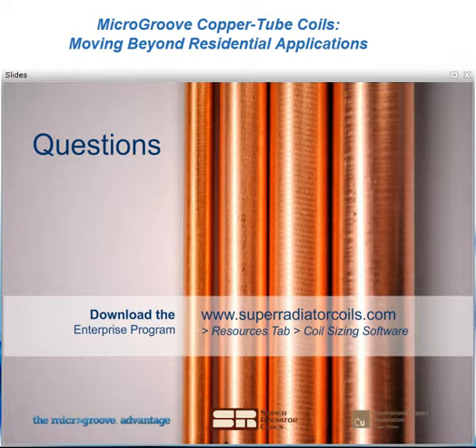The first one is, you have talked about less metal, but do the coils themselves actually cost less? That's a great one, Kyle. The coils we've been discussing and highlighting today, the condenser coils in particular, in many and most cases, there is a considerable cost savings in the unit cost of the coil itself. Just the metal reductions that we're talking about are significant enough. But it is important to know that with 5mm coils, sometimes the circuiting can be more complex. There are more circuits. The tubing can be more expensive. So there is an offset to some of that reduction.